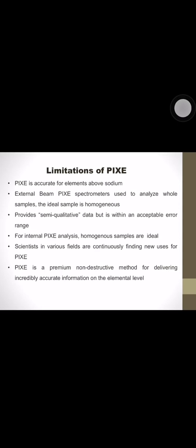If the sample is not homogeneous, it is best practice to test multiple sections and take the average of the quantitative results. This provides semi-qualitative data but is within acceptable error range. For internal PIXE analysis, homogeneous samples are also ideal as x-rays are emitted from only the top few microns and thus non-homogeneous samples may produce inaccurate readings.